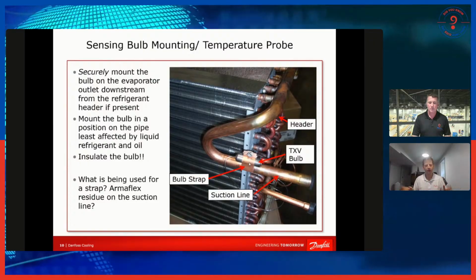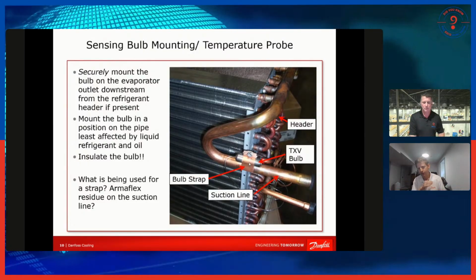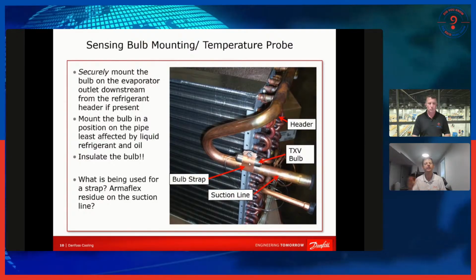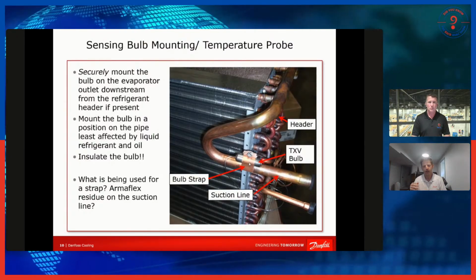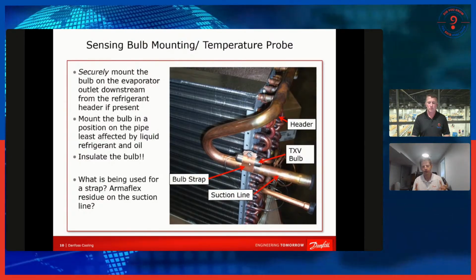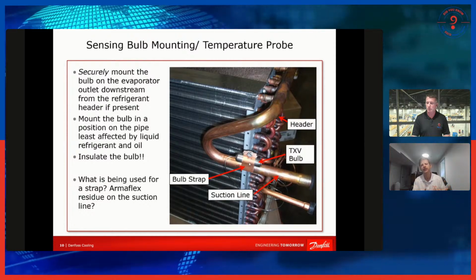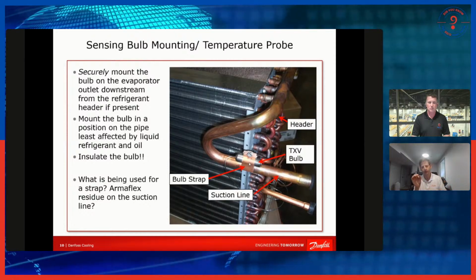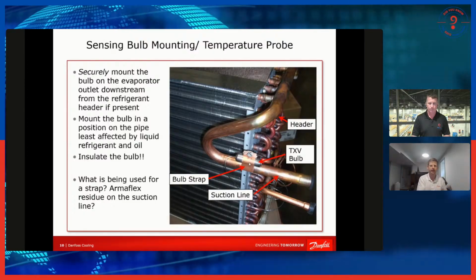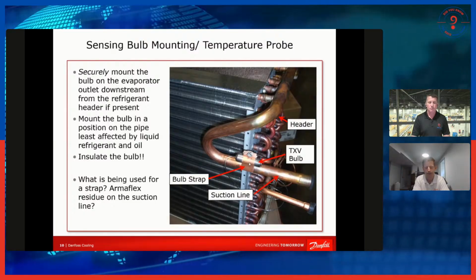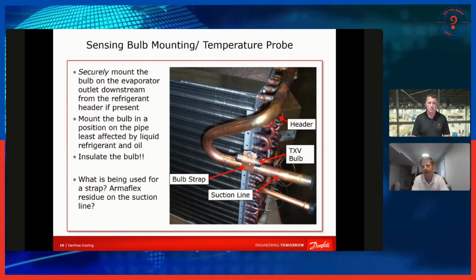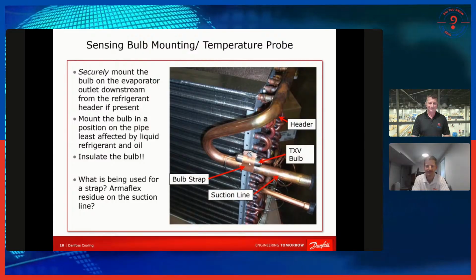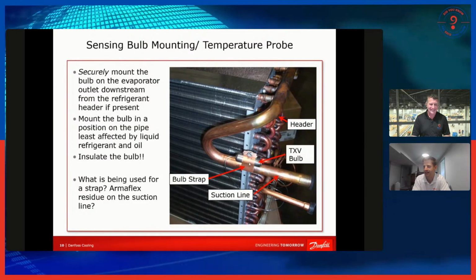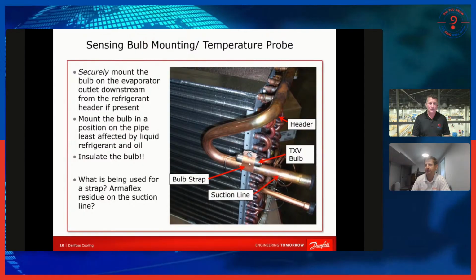It's not going to perform well because you're not actually going to be measuring the temperature of the suction line. It's going to be overfeeding a ton until you've got so much liquid flooding back that then finally the cold temperature starts to make its way through that gunk of Armaflex, and then it slams itself shut again. So yeah, that's definitely a thing to look for. That's an important consideration.